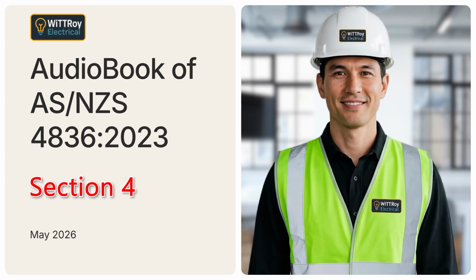Insulating barriers, covers, or mats must be used between conductors of different phases or voltages in the work area. Another approved procedure may also be used where suitable. The conductive path between a person and a conductor, between a person and earth, or between two people must be broken. This may be done using insulating barriers, insulating covers, insulating mats, insulating tools, or insulating gloves. If the work is left unfinished, the workplace must be left safe for other people. When the work is complete, electrical equipment must be returned to service in its original state, unless the changes have been approved.